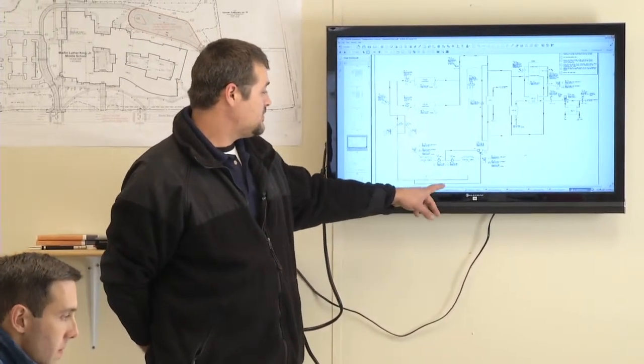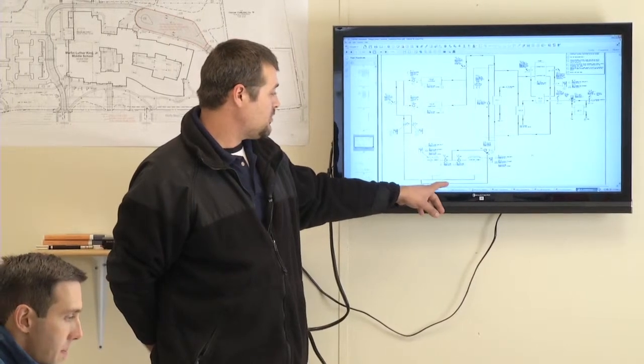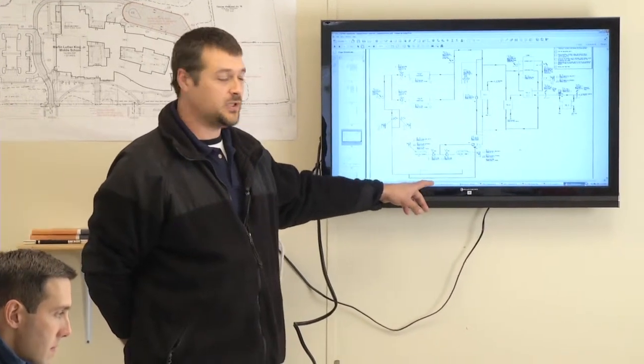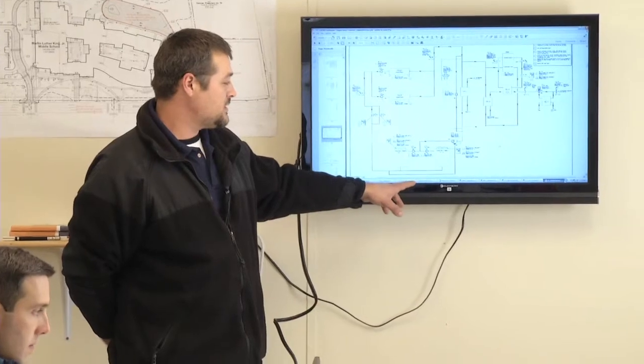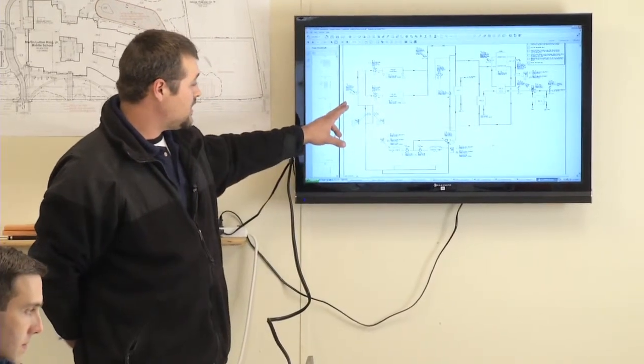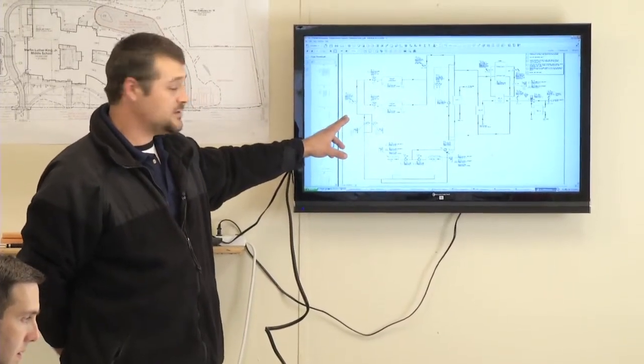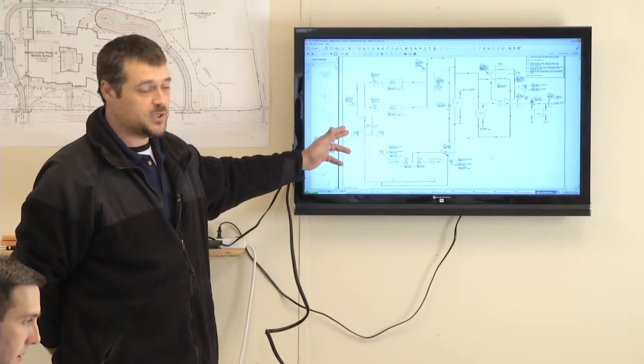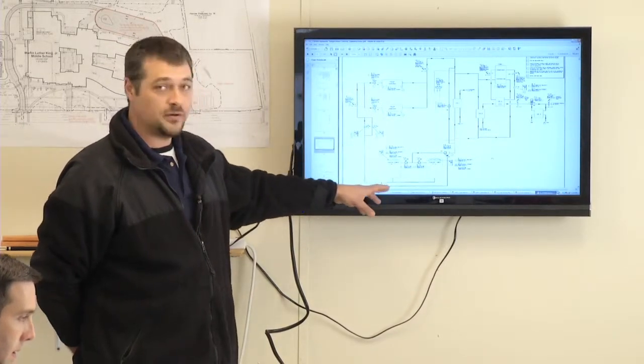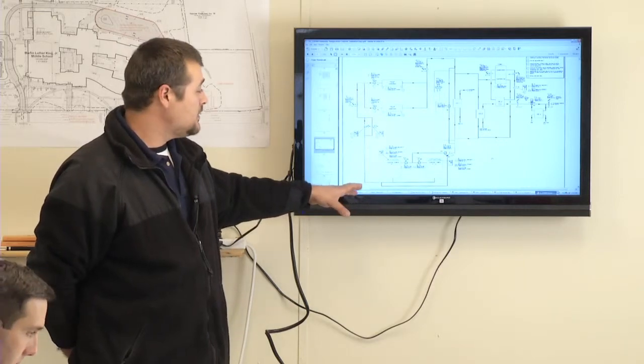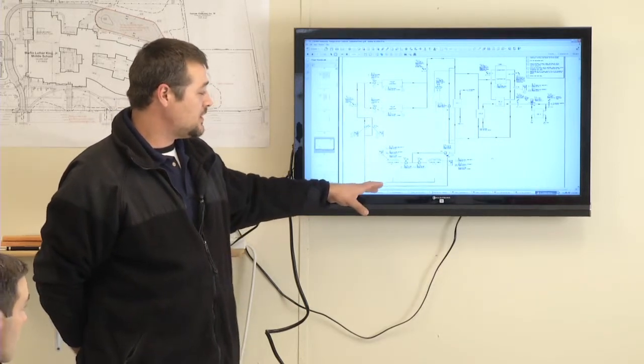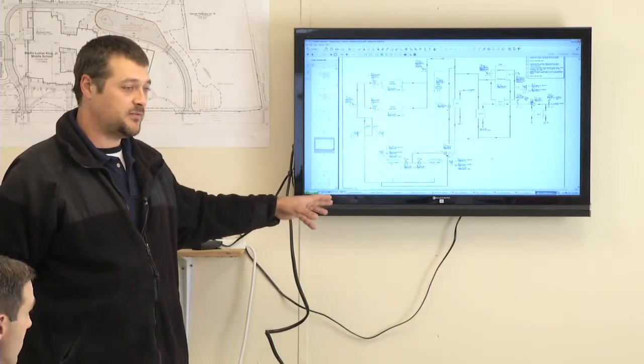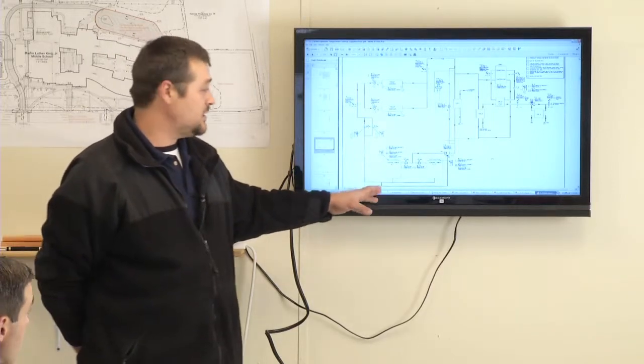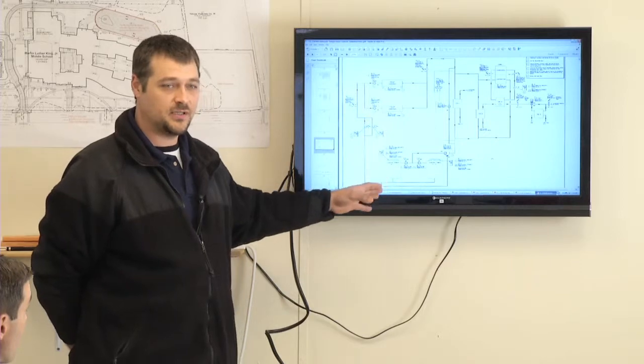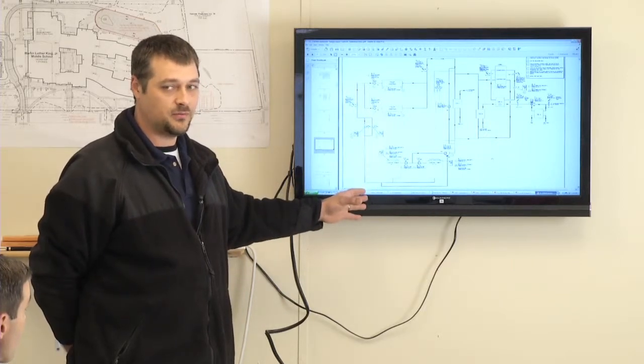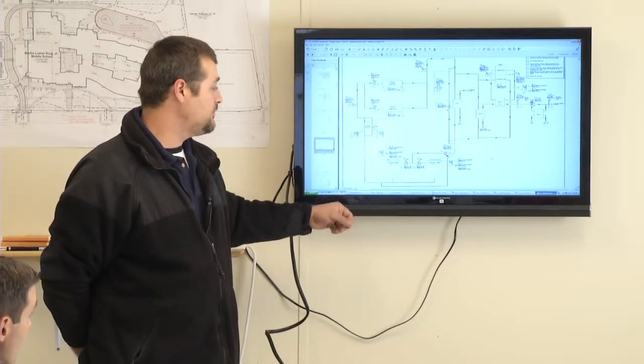We have two cooling towers that operate as lead lag. They switch on a weekly basis. They can also operate together. If our supply temperature sensor is greater than 78 degrees, that set point is adjustable, then we'll bring on an additional cooling tower. The chiller operates at an optimum condenser temperature between 75 and 80 degrees. And what I've seen is if there's some lag or an issue with the lead tower, we don't want to wait too long to bring on the secondary tower system.